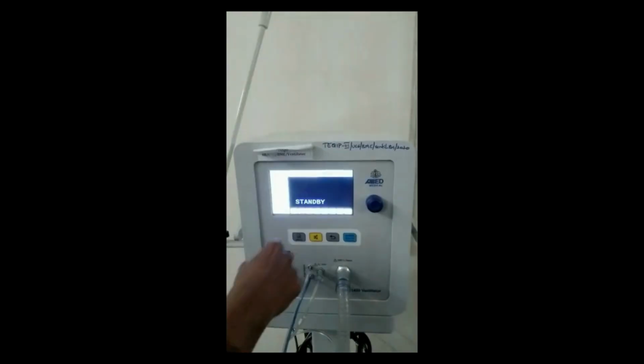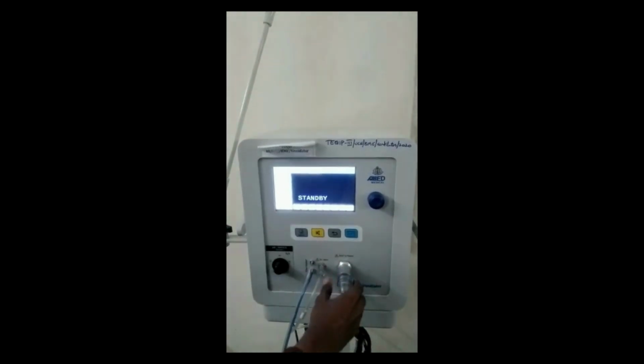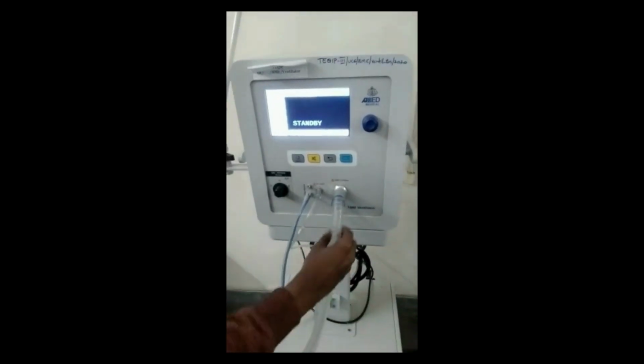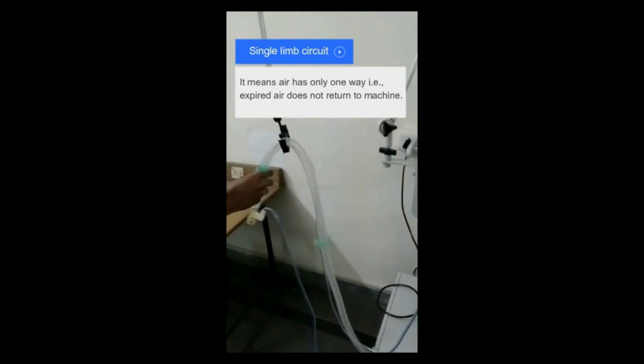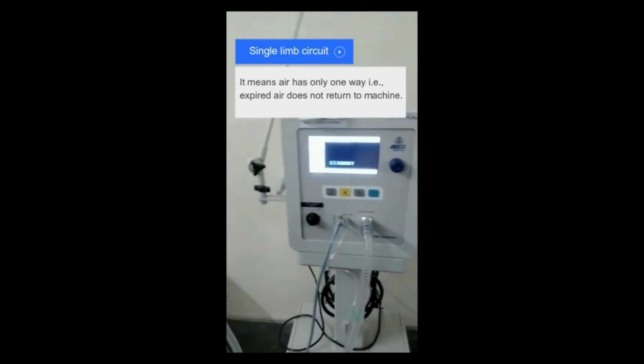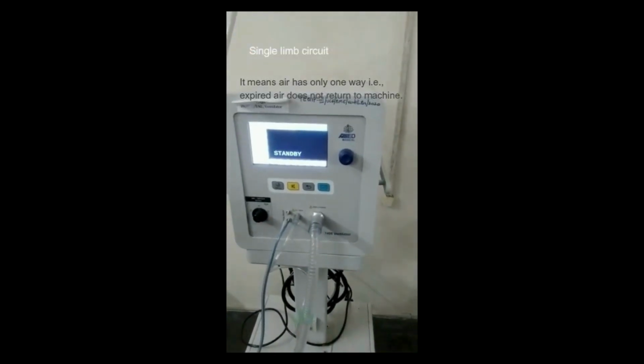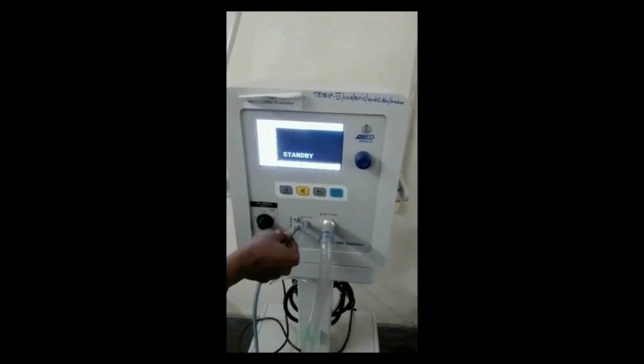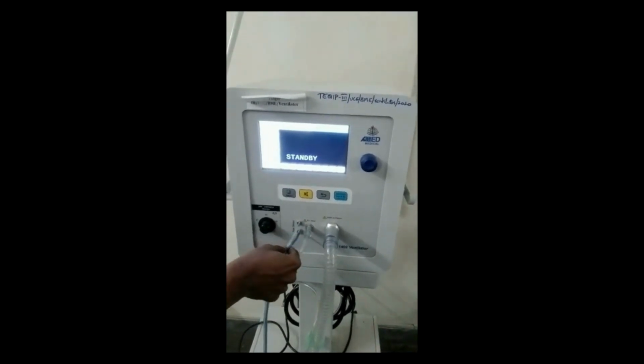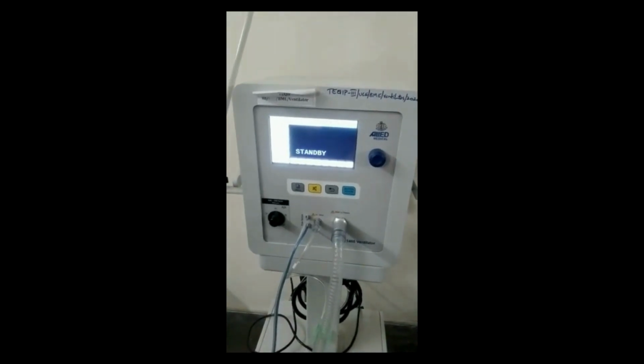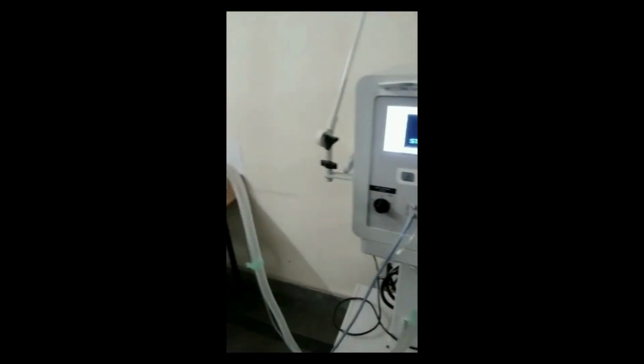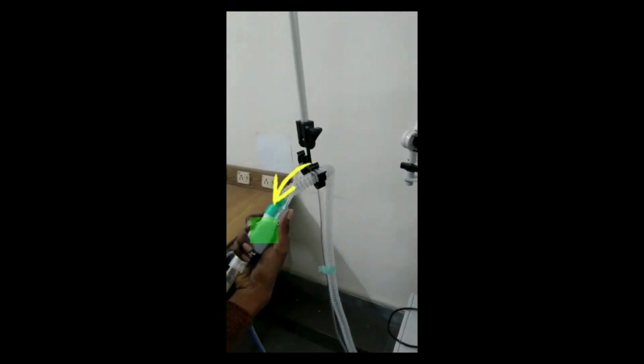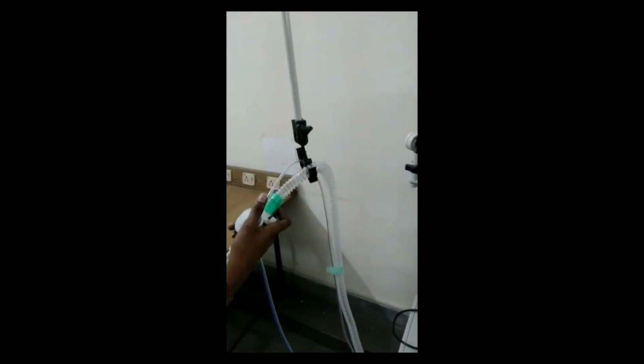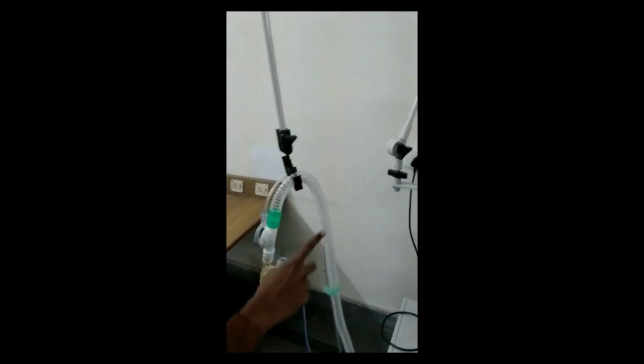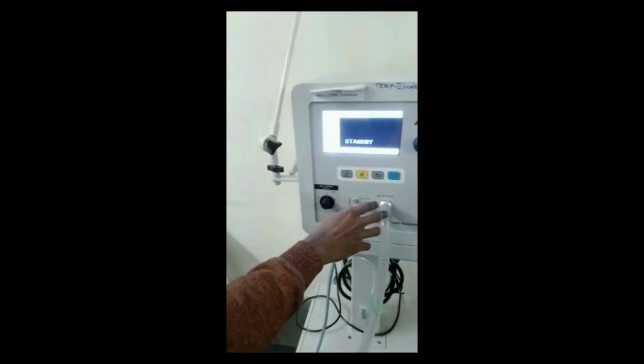This ventilator is compatible with the single limb circuit. This is the patient circuit in which one end of the tubing is connected to the ventilator and the other end of the tubing is connected to the patient. And this is the flow sensor for giving the measured values of the pressure being supplied to the patient. And this is the driving expiratory valve in the circuit. So exhaled air will be guided to this valve, and the pressure of the valve is controlled from here.